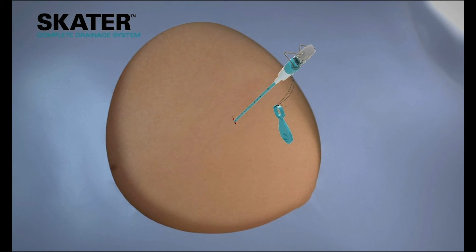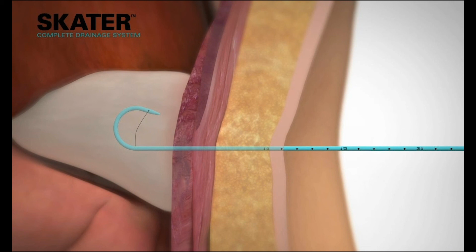After the catheter is positioned, the cannula is unlocked from the catheter hub. Holding the cannula stationary, the catheter is advanced further into the body to the desired location, ensuring that the pigtail is in the cavity. Then the cannula is fully removed. To lock the pigtail in its position, pull the locking tab gently to tighten the strings. While holding the strings taut, wind the string around the slot in the hub. Insert the clip onto the slot while holding the tab. Once secure, gently twist the snap-off tab and discard it.